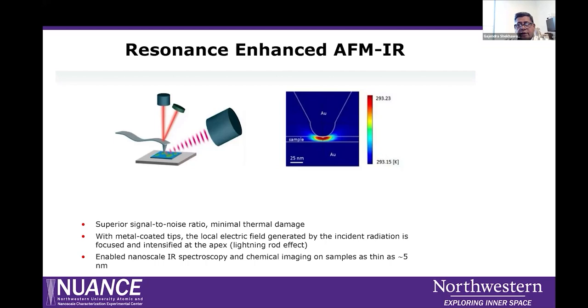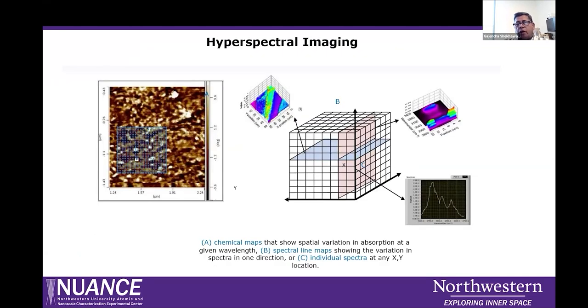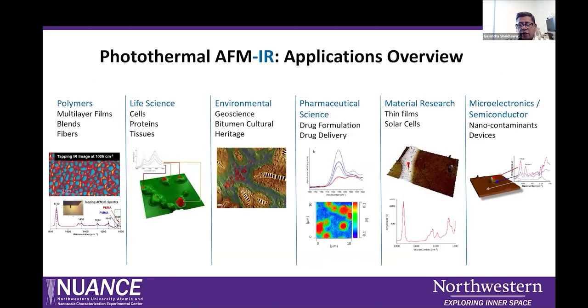Then you can see the resonance enhanced AFM-IR signal to noise ratio with a metal coated tip. It enhances nanoscale IR spectroscopy and chemical imaging on samples as thin as 5 nanometers. Then we can also do hyperspectral imaging. Rather than doing chemical imaging at a fixed wave number, you can scan the whole band of this IR spectrum and simultaneously do the chemical mapping. In the case of hyperspectral imaging, you can just draw a line and go pixel by pixel. You can draw a line across the different regions of the sample and get a different IR spectrum. So that option we have.